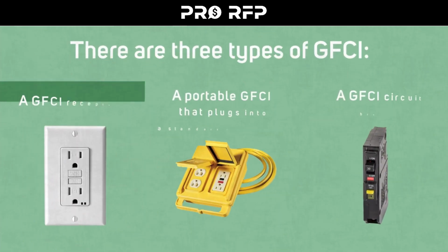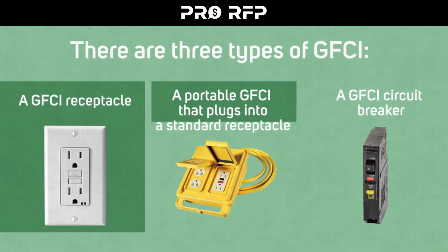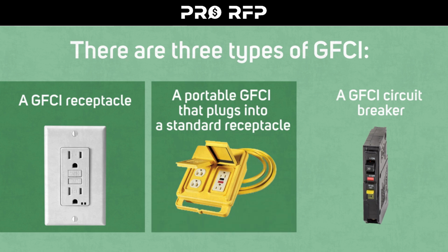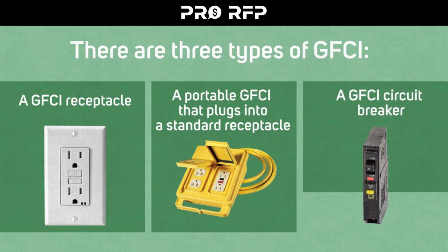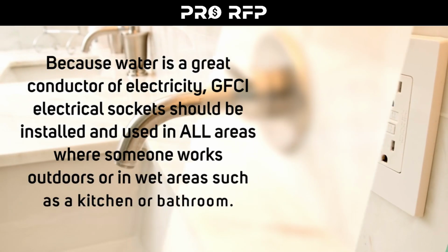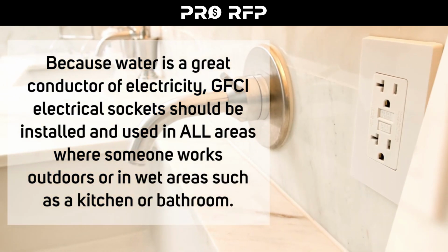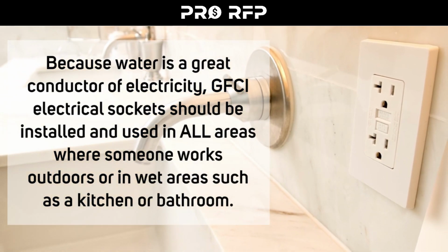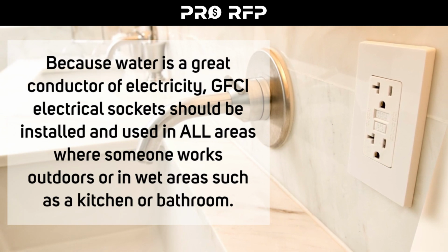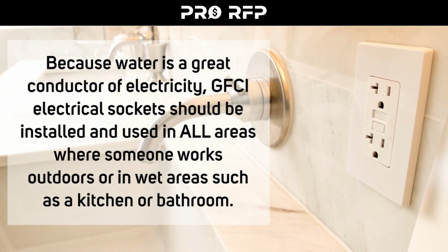There are three types of GFCI. A GFCI receptacle, a portable GFCI that plugs into a standard receptacle, a GFCI circuit breaker. Because water is a great conductor of electricity, GFCI electrical sockets should be installed and used in all areas where someone works outdoors or in wet areas such as a kitchen or bathroom.